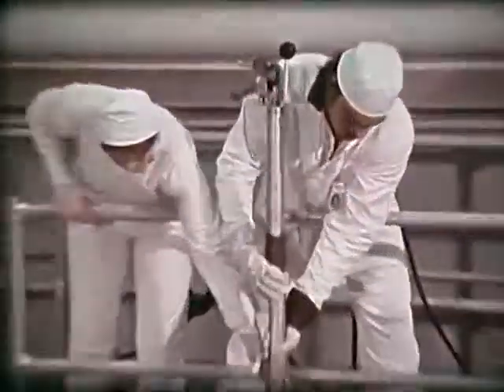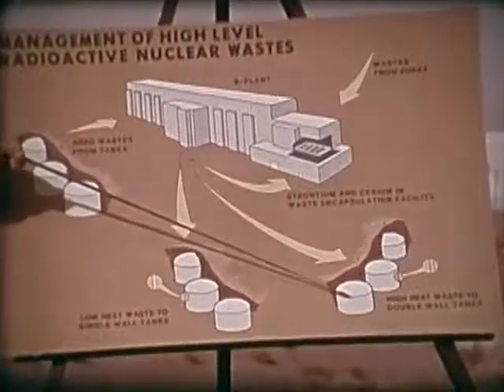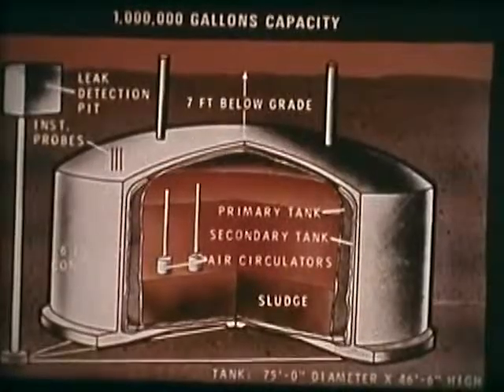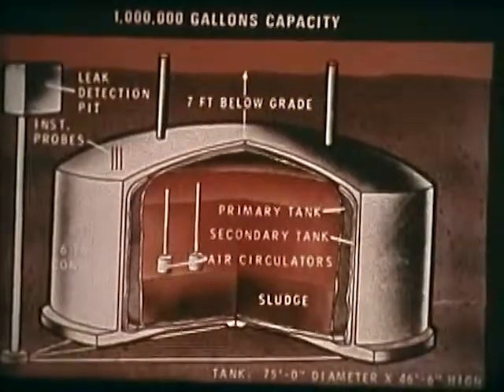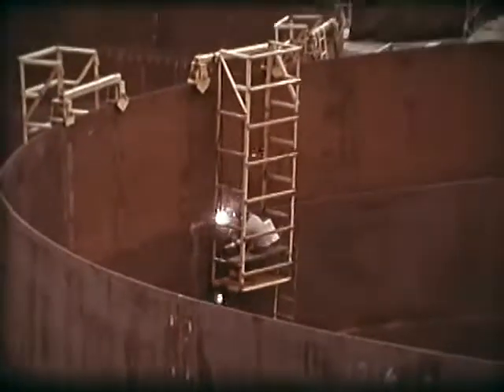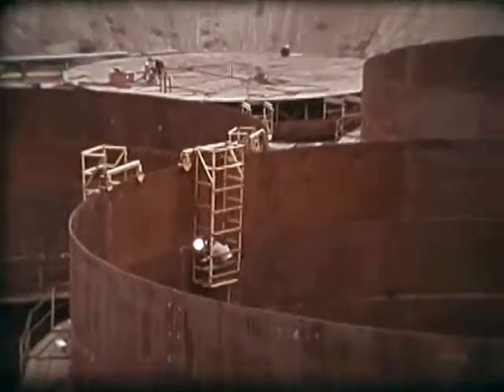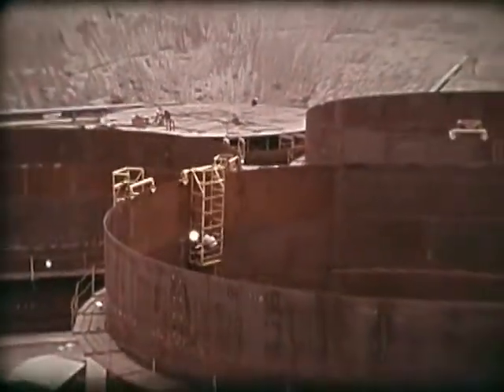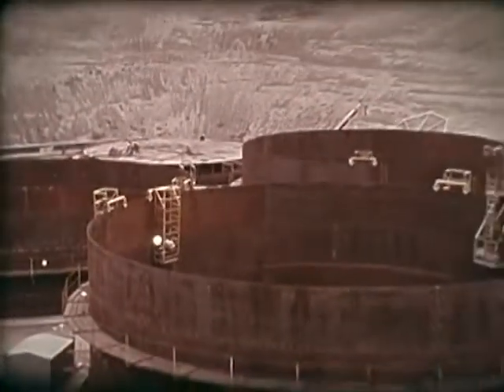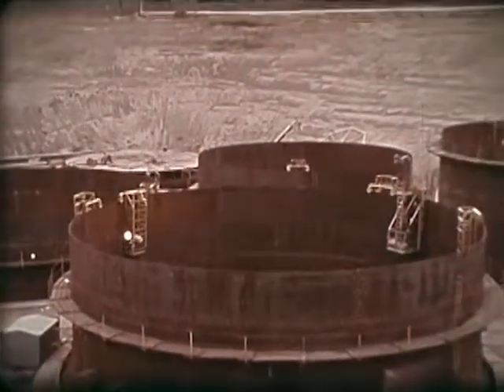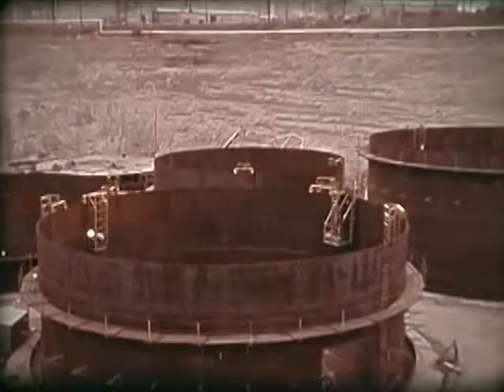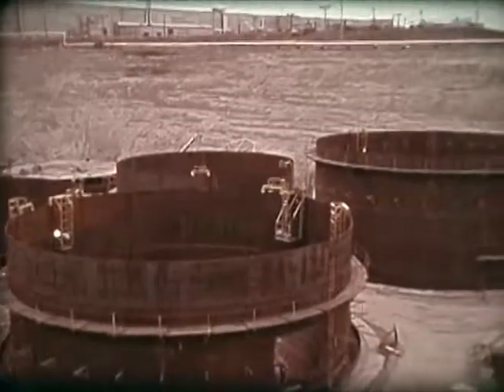The remaining liquid is transferred through underground piping to high-integrity double-walled tanks. These underground tanks are concrete tanks with double steel liners, fitted with several types of instrumentation, including liquid level measurement devices and leak detection monitoring in the annular region between the steel walls and the outside, to detect any potential leakage.